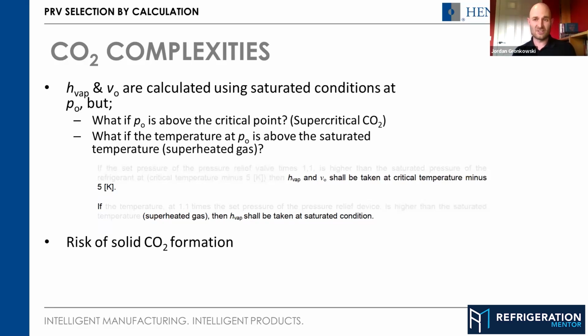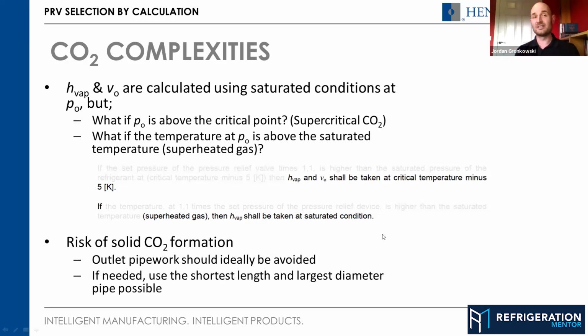Again, that's something mentioned in the standard, but they don't give much advice on how to avoid it, except for saying it should be avoided, which is helpful. The advice that we typically give is that ideally outlet pipework should be avoided altogether, and the valve should just be allowed to vent. There are cases where that's not possible, because maybe the valve is at head height somewhere where somebody might be working, and you don't want that to discharge straight into somebody's face. Could be very dangerous. So if you do need to use some outlet piping to change the angle of the outlet or flow, generally try to use the shortest length and the largest diameter pipe possible.